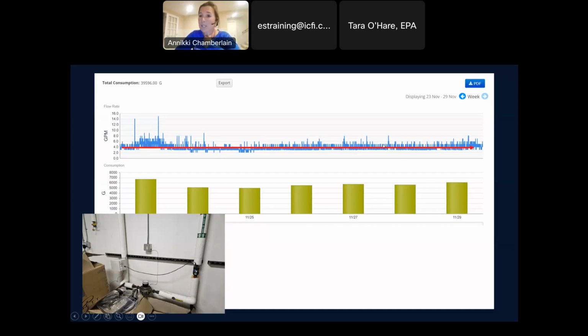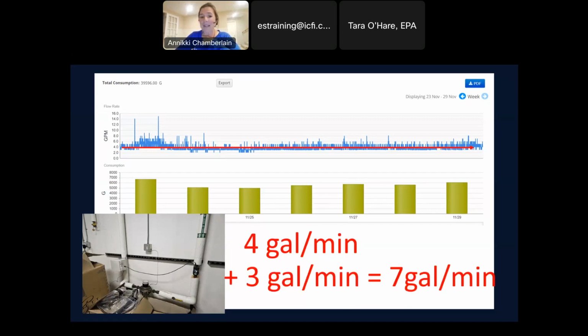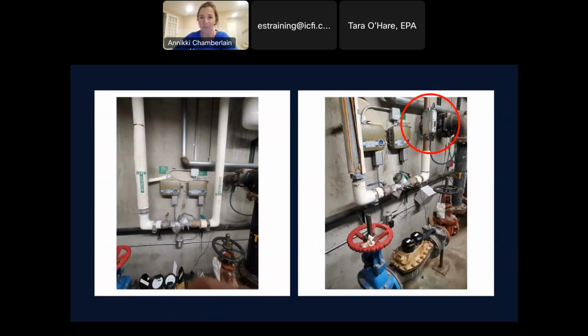And so we're seeing the cooling tower is running at about 4 gallons per minute because it's also having a problem. So we got 3 gallons a minute, we got 4 gallons a minute, so we got 7 gallons a minute. So we basically have found our problem. And so they may want to install a permanent meter on that line so they can keep track of it, or maybe this was good enough and we can move on, but it saved a ton of time. It basically took us a couple minutes to install the meter, and now we can isolate it to a location, and we're going to go find it. I'm pretty sure I know what it is, though.